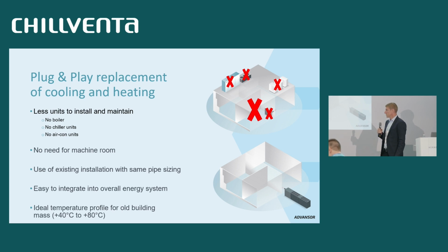So, the CO2 plug-and-play heat pump: we can easily replace fossil fuel boilers. We can easily replace the air conditioning units. When we look at the plug-and-play heat pump, we have a temperature profile of 40 degrees inlet and 80 degrees outlet, which is quite nice if you look at the condensing gas boiler. So it's quite easy to replace.